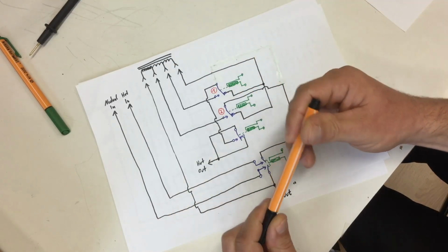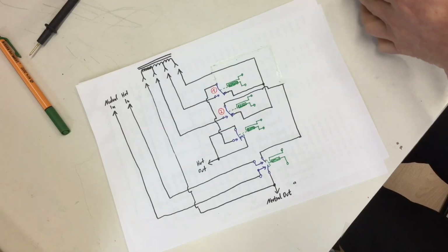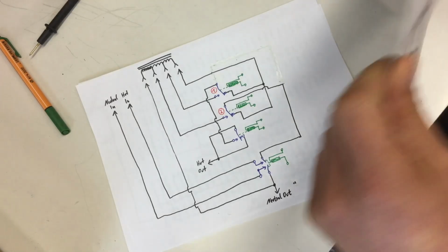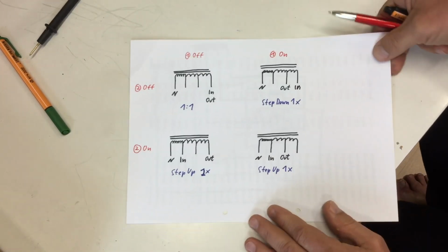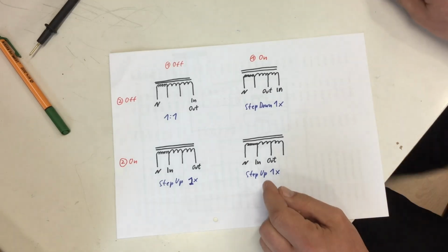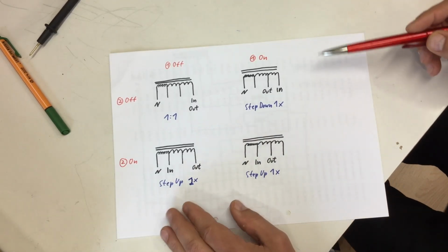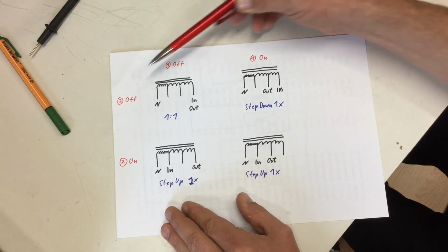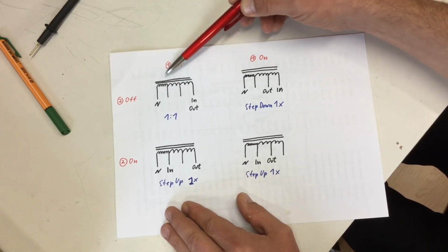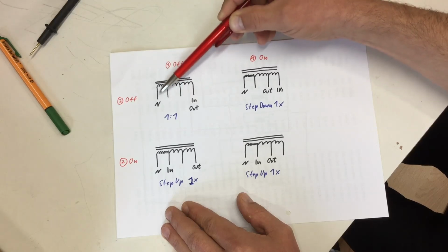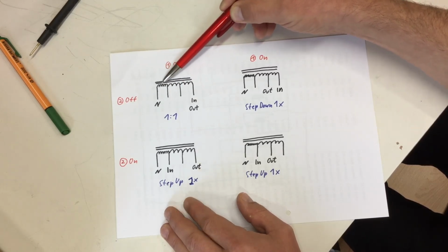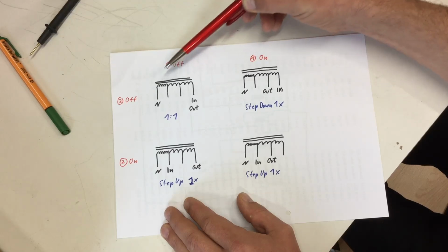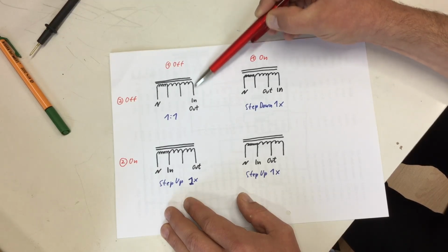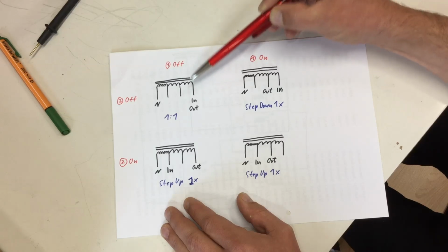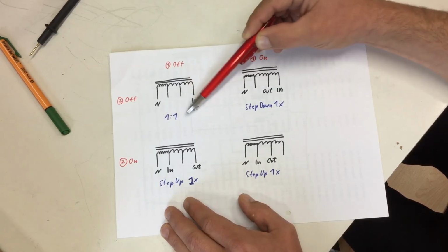Before tracing everything here manually, I made a little table. So basically if relay 1 is off and relay 2 is off, neutral is always connected by the autotransformer to the left side here with the many windings. Both in and out are connected to the same output of the autotransformer, so you have one-to-one.